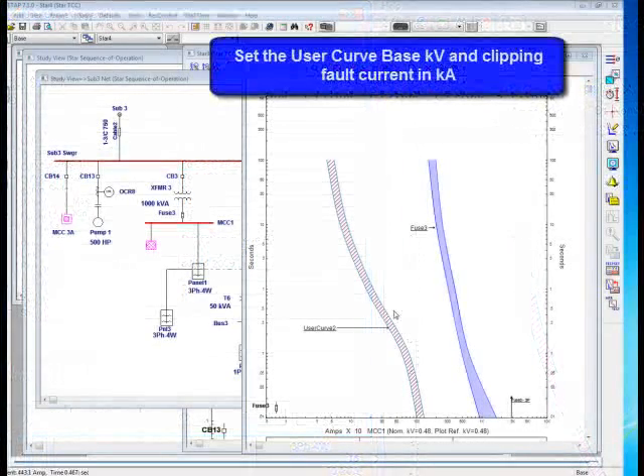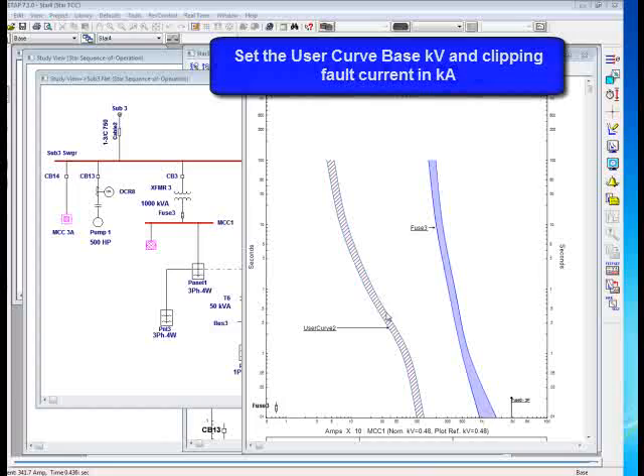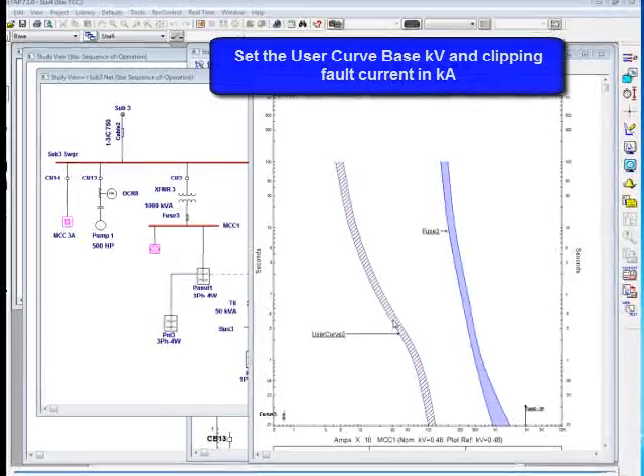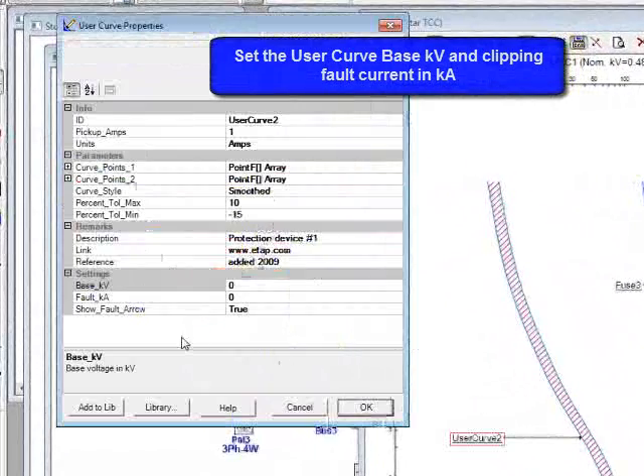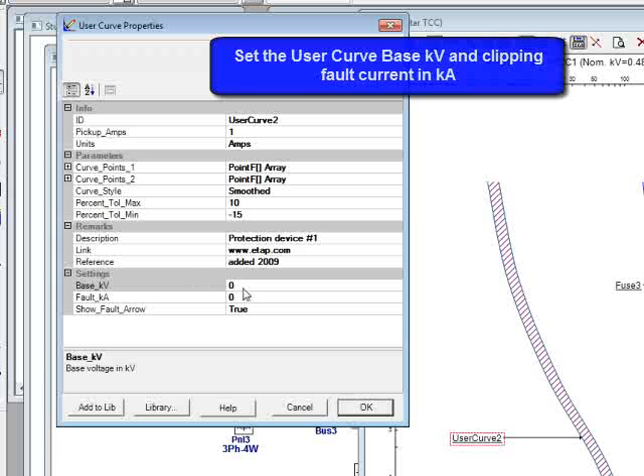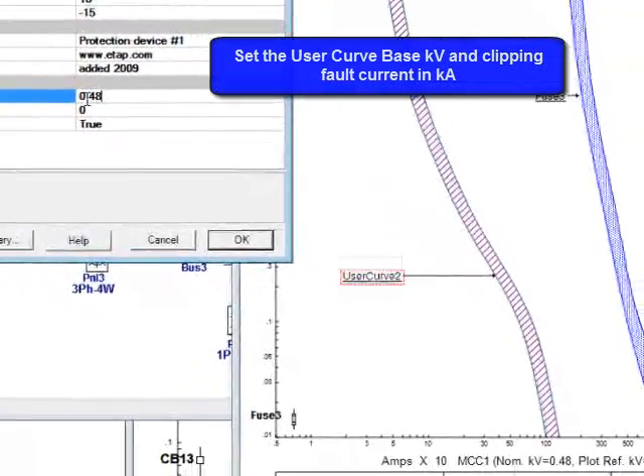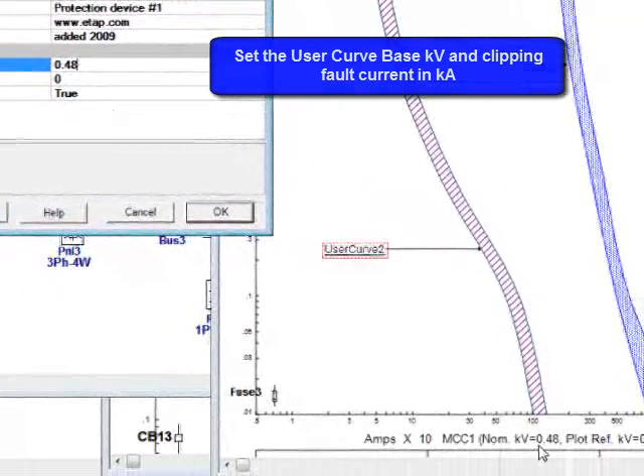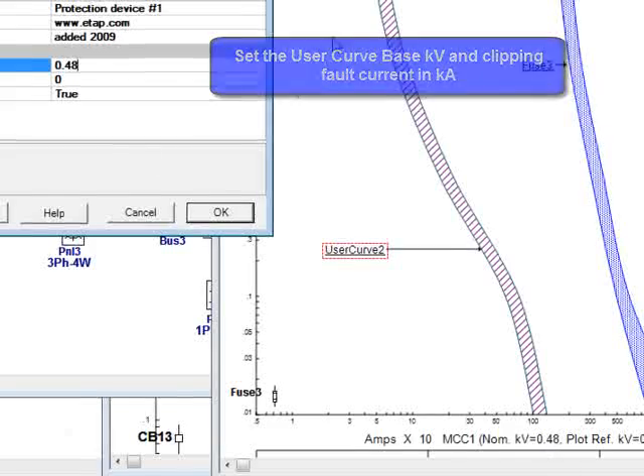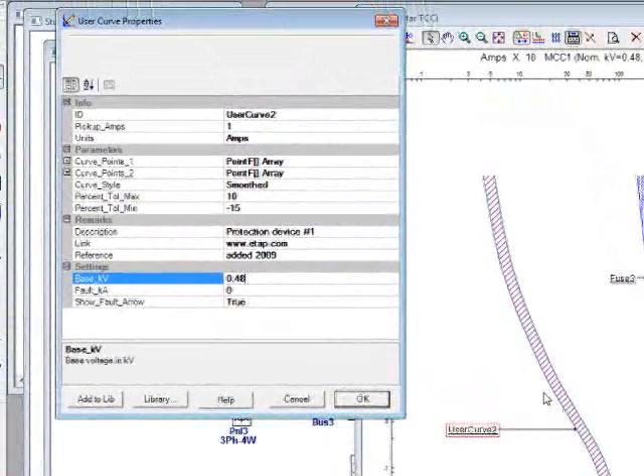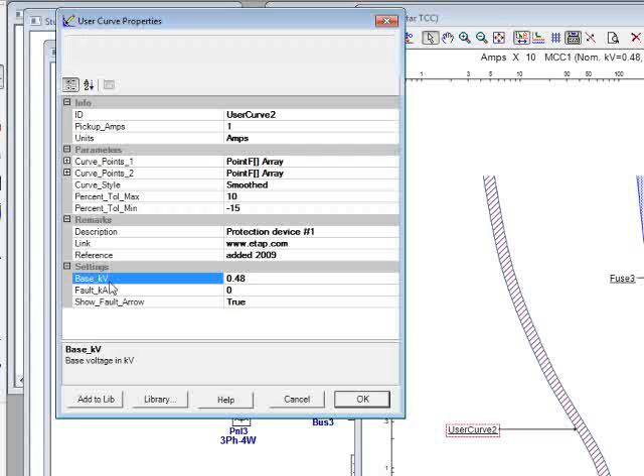You're also capable of adding the base KV to the user curve. Just simply double-click on the user curve and specify the base KV in the setting section. The base KV by default is 0, but you can enter whatever you want it to show. If you put the same base KV as the plot KV, the curve won't shift. But if the base KV is different than your plot KV, you will see the curve is going to shift.